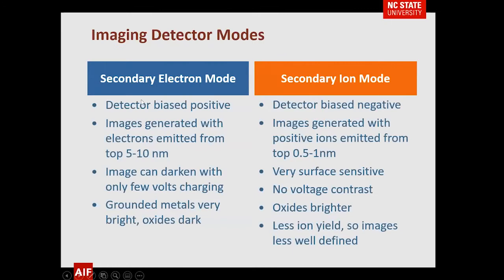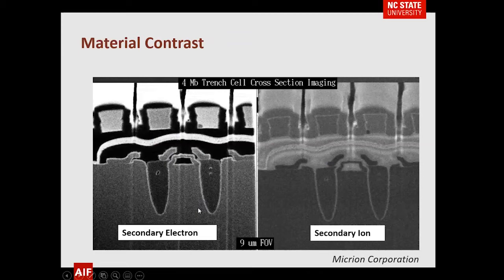If you have a detector where you can look at secondary ions — mainly by biasing the detector negative — most of the ions that come off are positive. For secondary electrons you bias positive to detect the electrons. Here's a cross-section of a semiconductor feature: in the secondary electron image there is a lot of black area from charging, but the secondary ion image clearly delineates a number of layers you can't pick up in the electron image. The combination of the two can be very useful.